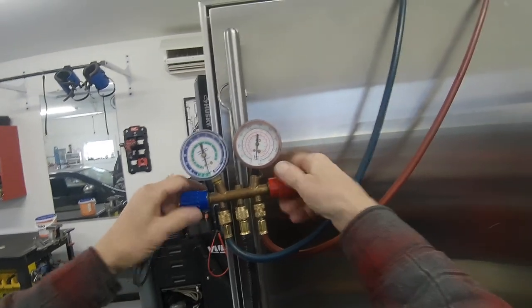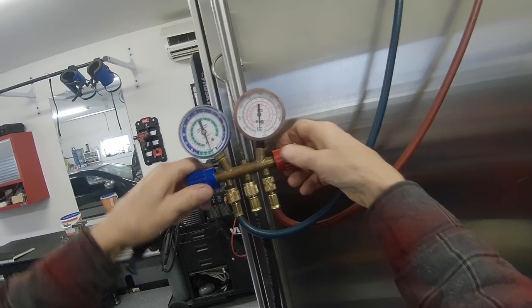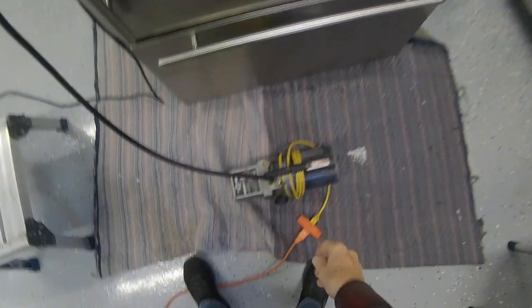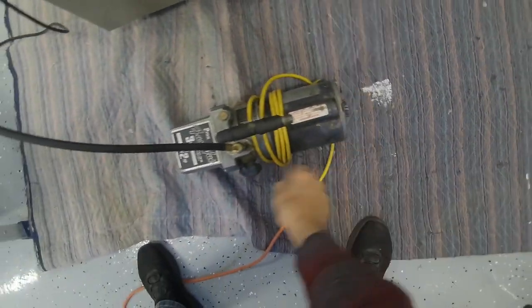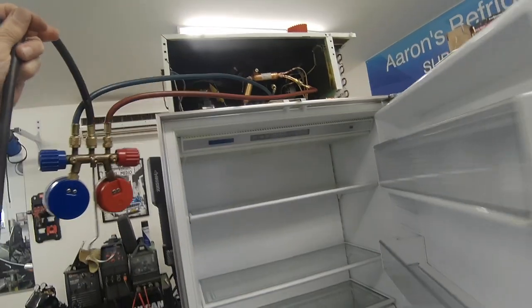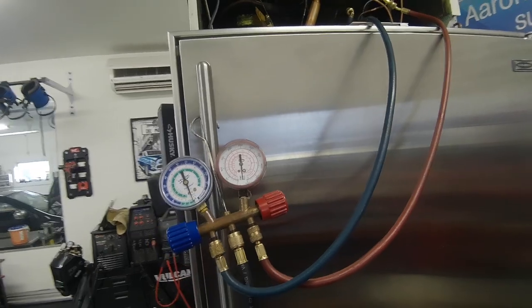Okay, we're looking good here. Shut this down. Alright, we got eight ounces of 134A. This has the original evaporator coil in it, so we're going to weigh in eight ounces.